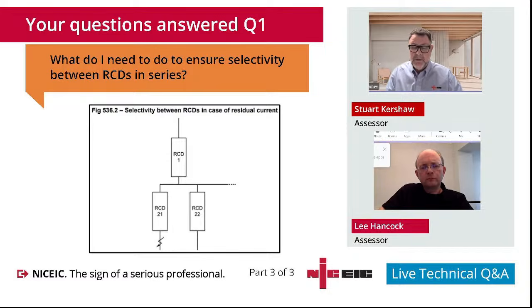So yeah, for further information, really consult manufacturer's data for setting up of S-type devices, Sam. Yeah, but it's those things that we always remember, the 3:1 ratio. So upstream should be 3 times the rated value, and S-type for upstream devices.